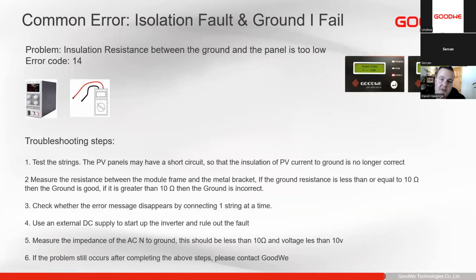So one of the most common faults we'll have is an isolation fault, or a Ground I Fail. So isolation fault and Ground I Fail are similar conditions. So it's essentially leakage current on the ground. So isolation fault is always going to be more on the PV module side, and Ground I Fail is going to be more on the utility side. So if our grounding is poor, from the utility side, we might have an elevated voltage between neutral and ground. We will have the Ground I Fail.